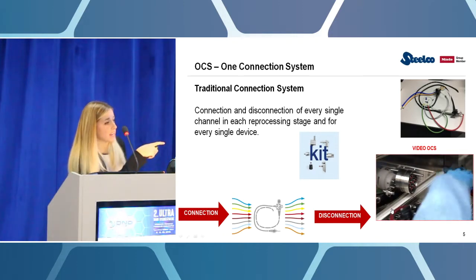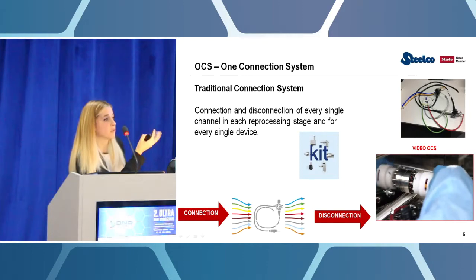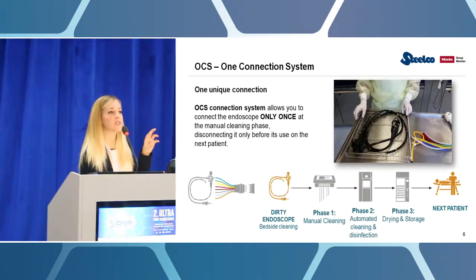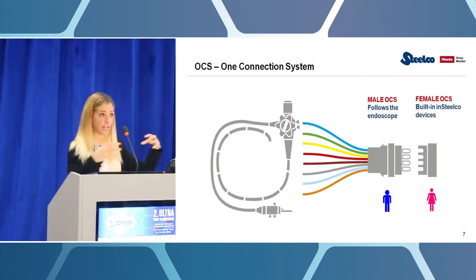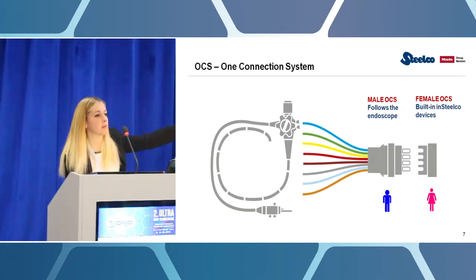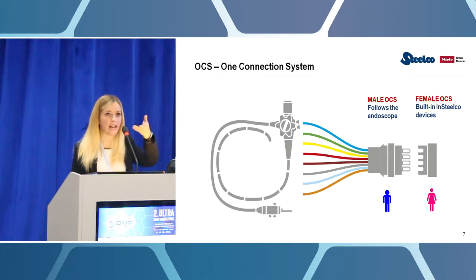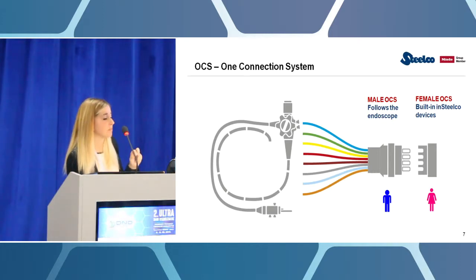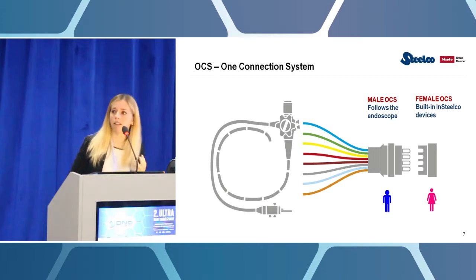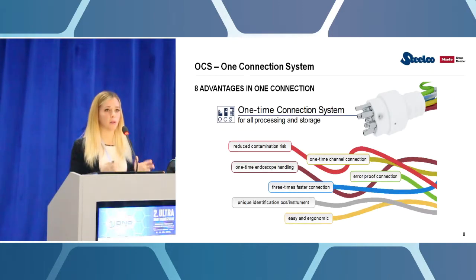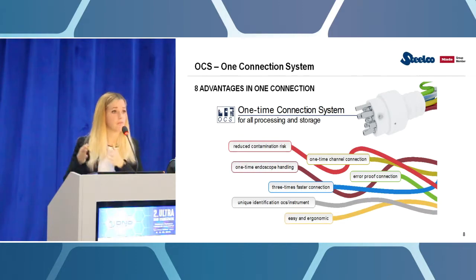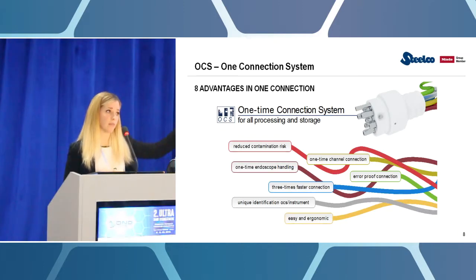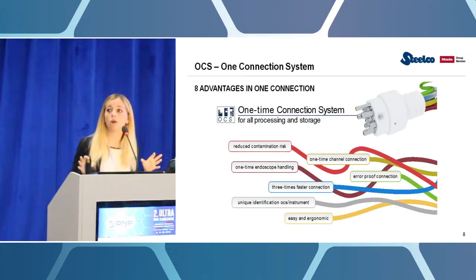Here you see how it is made. We have the octopus part, let's say, the one that looks like an octopus that is attached to the endoscope. And then you have the female part that is built inside all our devices. So what's the benefit of using this system in comparison to the traditional connection systems? First of all, you gain time, because as we said, the connection part will be done only once instead of several times.